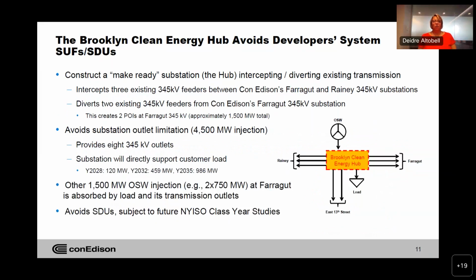Our design also addresses maintaining the reliability of the local system. This is where the electrical location of the hub is important. Take a look at the graphic in the lower right corner of the slide. This make-ready hub will intercept 3 existing 345 kV feeders currently connecting the Rainey and Farragut stations. Additionally, 2 feeders currently connected to nearby Farragut station will be relocated and connected to the Brooklyn hub.